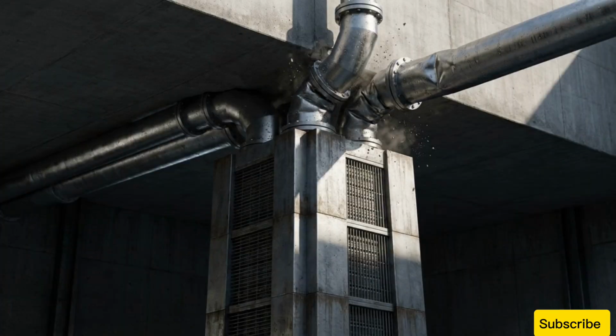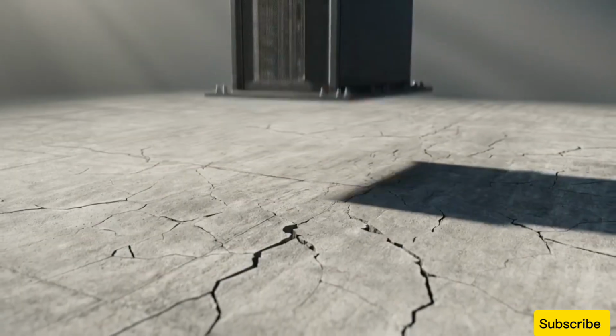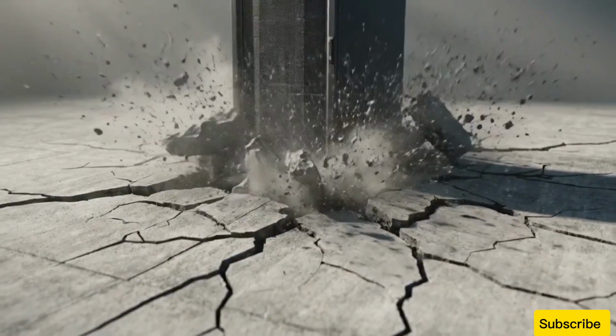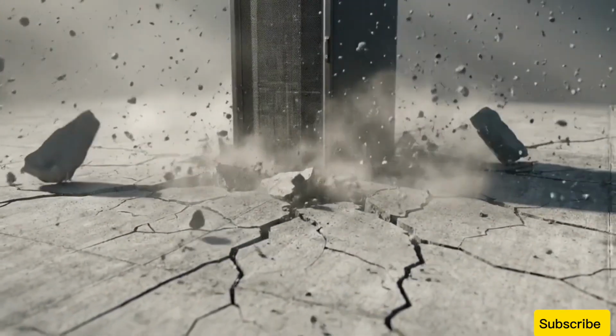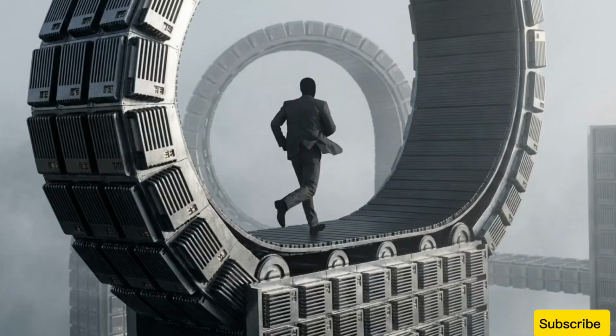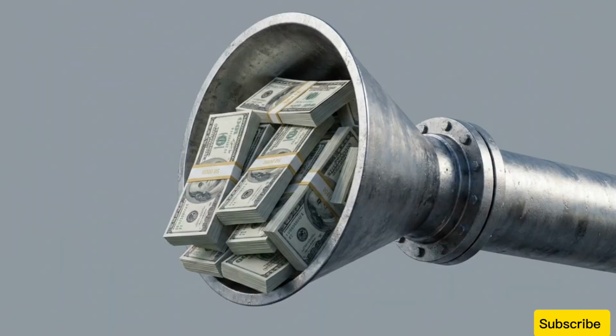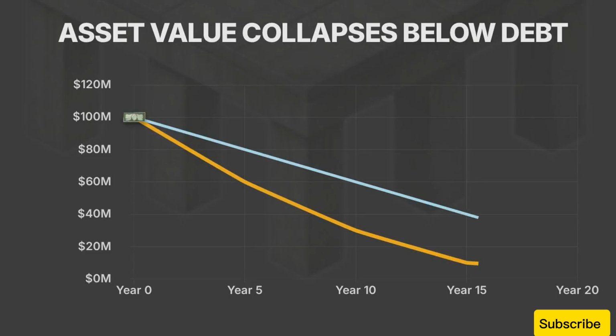This creates the retrofit trap. Older buildings lack the vertical clearance for massive liquid cooling ducts, and their standard concrete floors will literally crack under the immense weight of these new high-density AI clusters. Independent operators are trapped on a relentless capital expenditure treadmill. You must continuously inject tens of millions of dollars into new cooling infrastructure just to keep the building relevant, rebuilding an asset that depreciates much faster than the mortgage used to finance it.